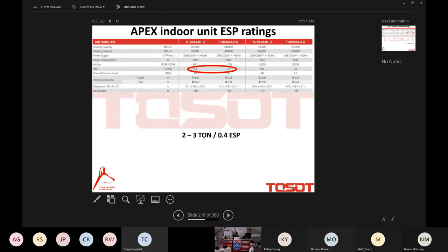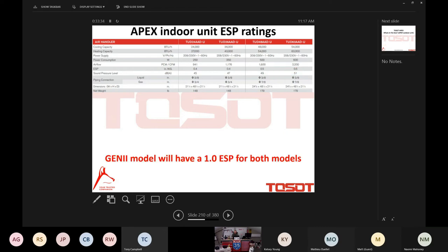Here's another issue between Gen 1 and Gen 2, my friends. Gen 1, the 2 and the 3 ton, 0.4 external static pressure. The 4 and the 5 ton, 0.5 external static pressure. Here's the benefit of the Gen 2. 1 inch of external static pressure for both models. That's a beautiful thing.